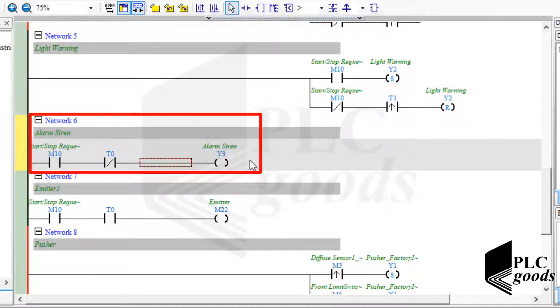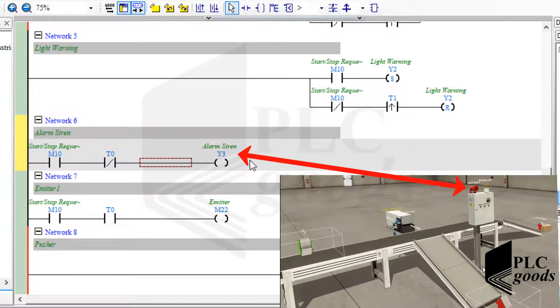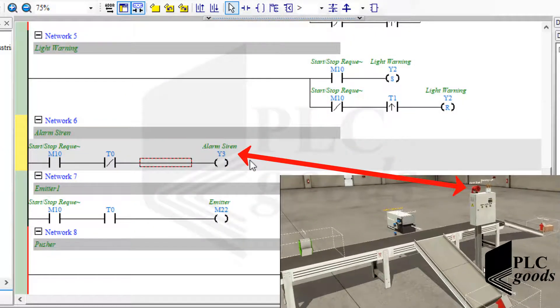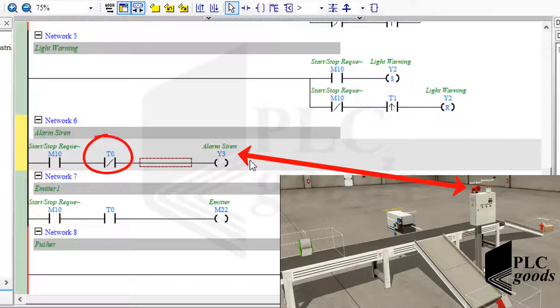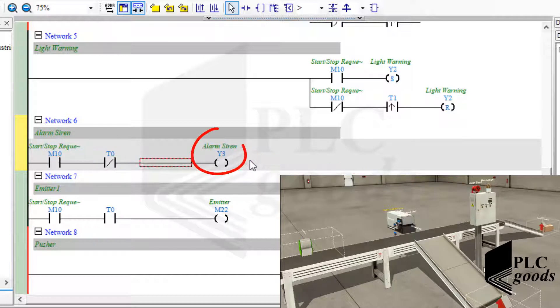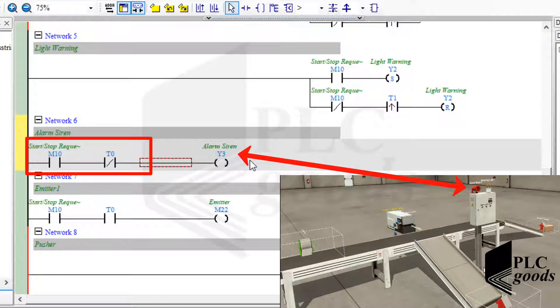Based on this network, the alarm siren will be on when PLC detects a start request and the first timer time is less than its defined time. Note that I used a simple coil instead of using set and reset instructions. So when this condition is not true, the alarm siren will be off automatically.